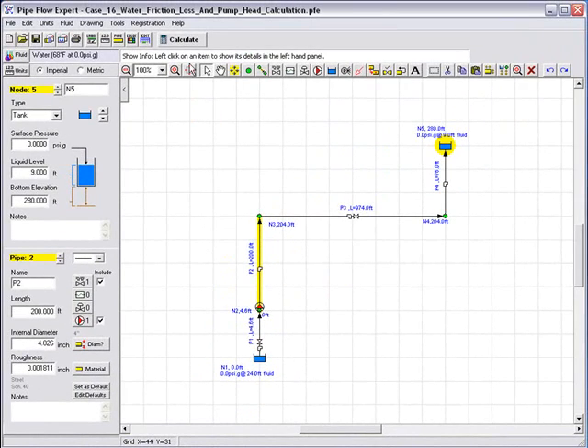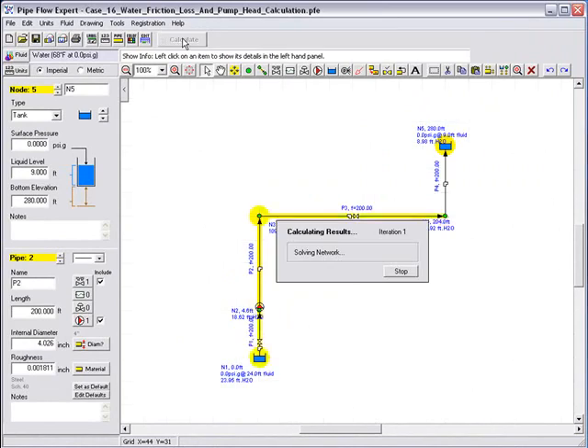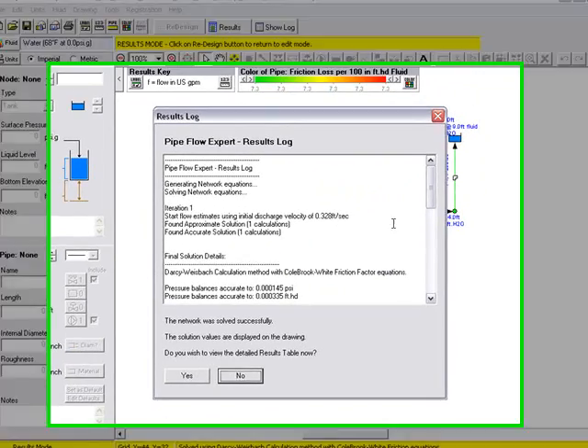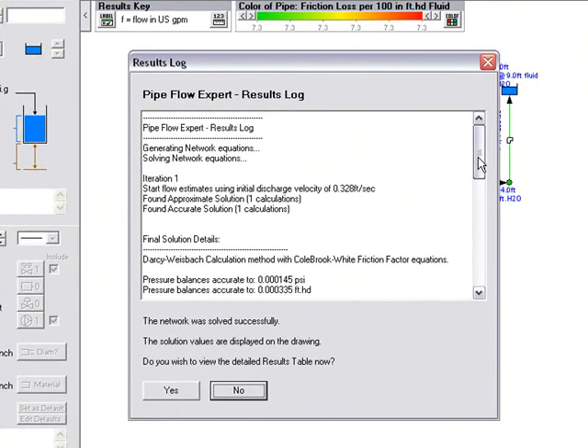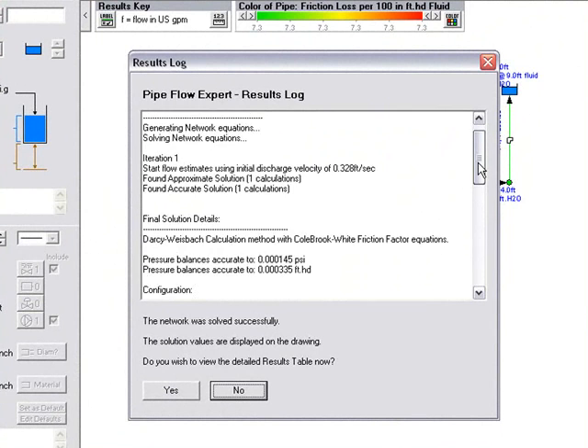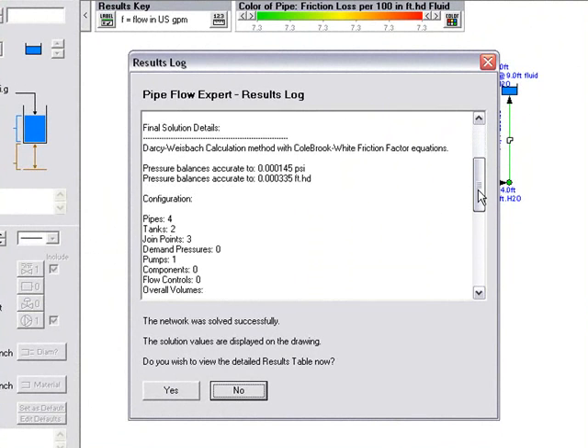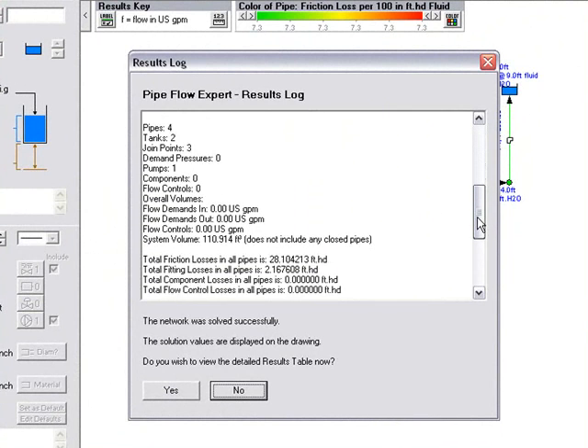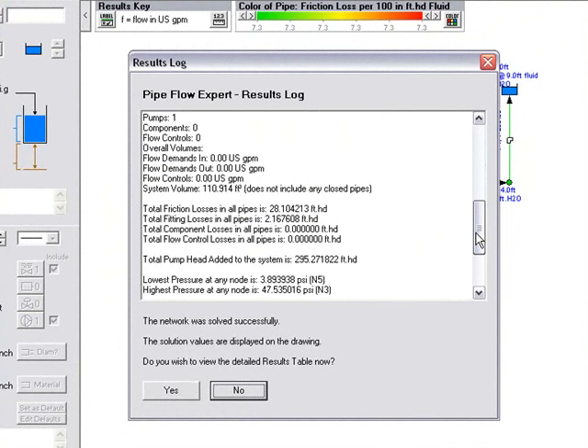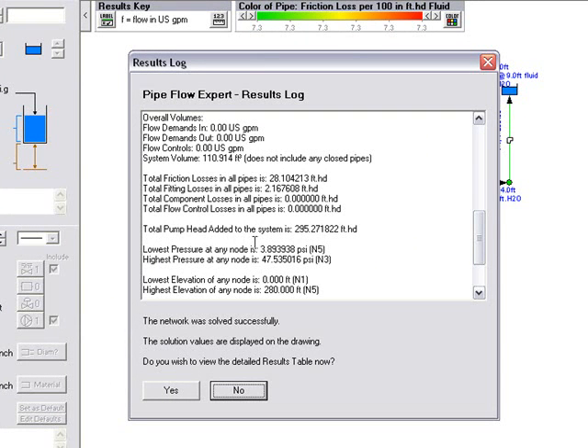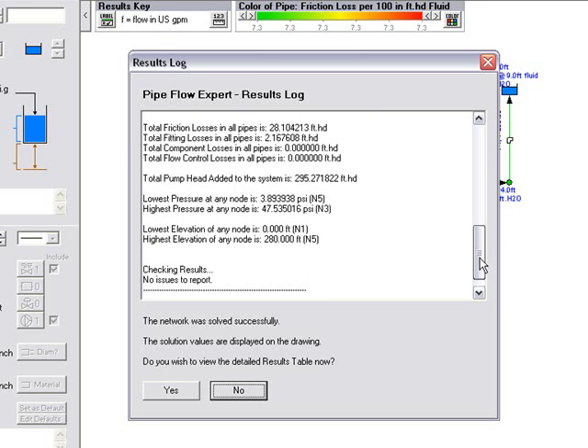If we run the calculation, we click on calculate. The system is solved and we can review the log. This gives us information about the method used to solve the system and gives us information about friction losses and fitting losses. We can also see that the total pump head added to the system is 295.27 feet head. There are no issues to report, and we are asked, do we wish to view the detailed results table now?